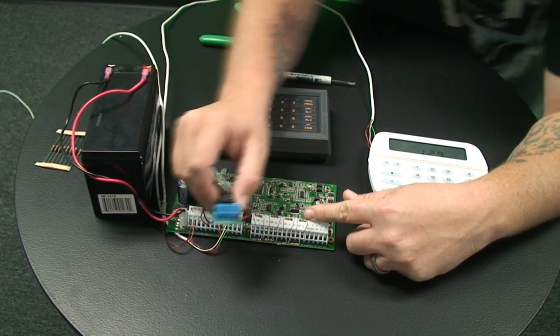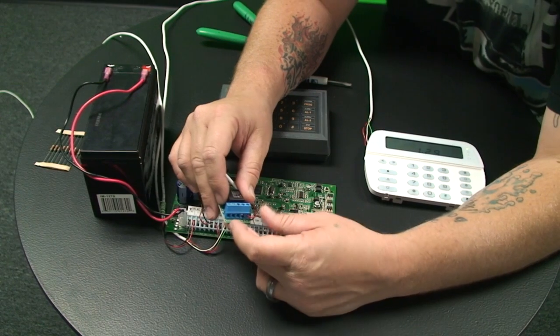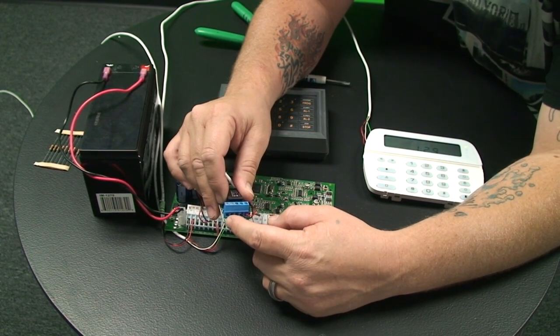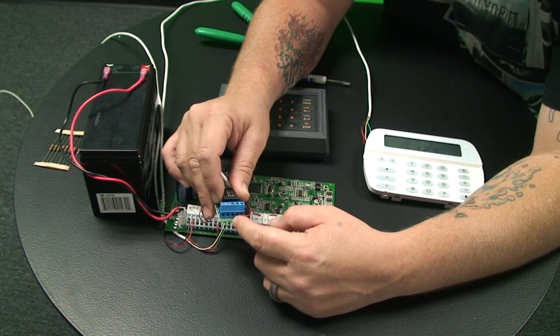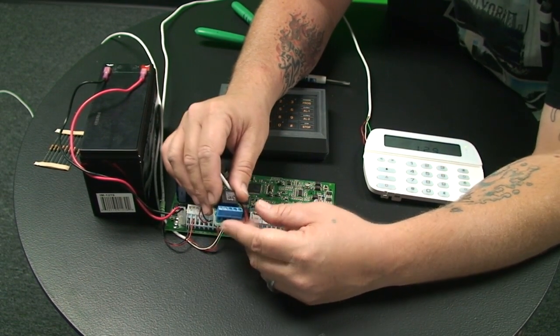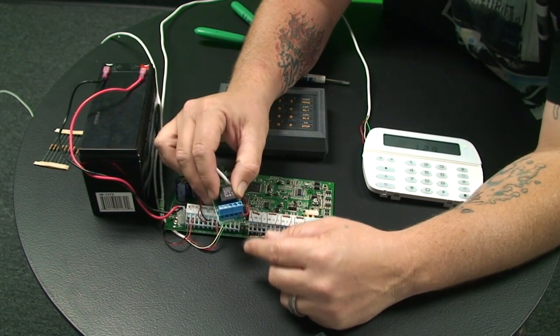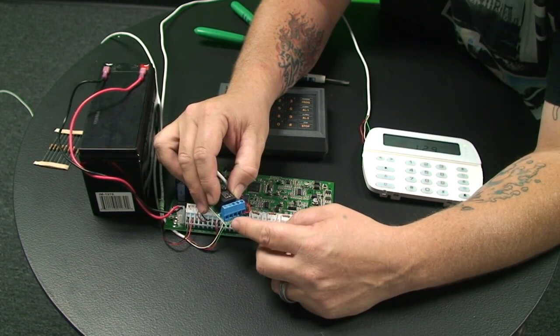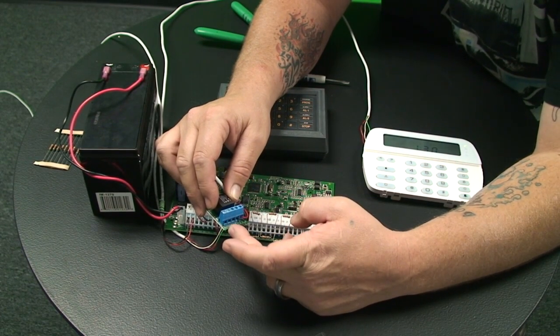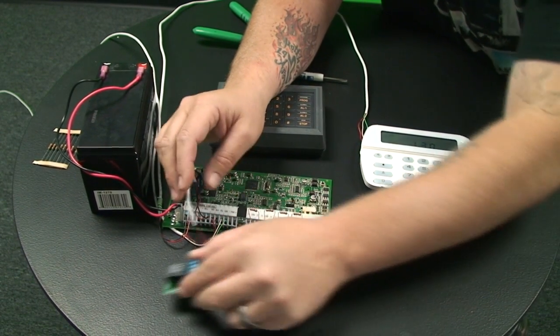So from here, this relay has three more terminals. It has an NO, a COM, and then an NC. The NO means normally open, the NC is normally closed, and the COM is common. So what we're going to do here is this particular dialer likes to have the normally open. It likes to see the closure when it goes into an alarm. So we're going to wire from the normally open and the COM to the inside of this dialer.